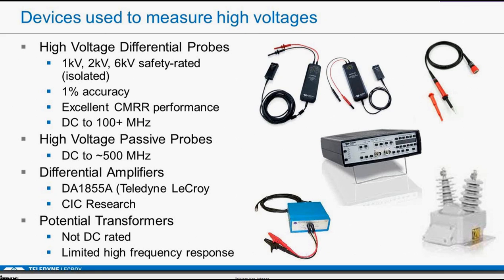Devices used to measure high voltage range from a high voltage differential probe used with a scope. They might have ratings from 1 to 2 kV or 6 kV safety rated. This is our probe here. It's an HVD series probe, which has very good accuracy and very good performance and fairly high bandwidth. A lot of people use high voltage passive probes, which go up to similarly high voltages or perhaps even higher. Beyond about 6 kV, you're probably using something like a voltage potential transformer, maybe not a handheld device, but now something like a differential amplifier, which would be something like this made by CIC Research, which can go very, very high in voltage. Or for lower voltages on the device side, maybe something like this differential amplifier, which we manufacture.